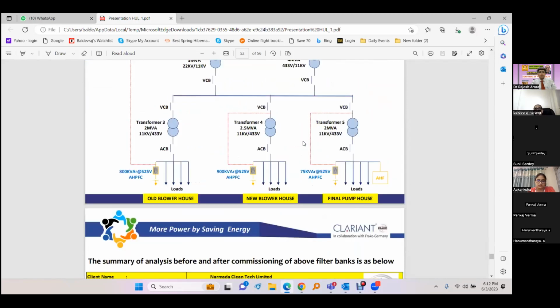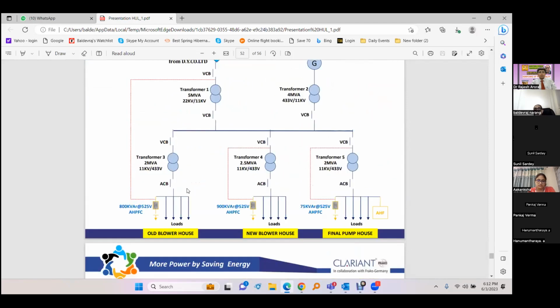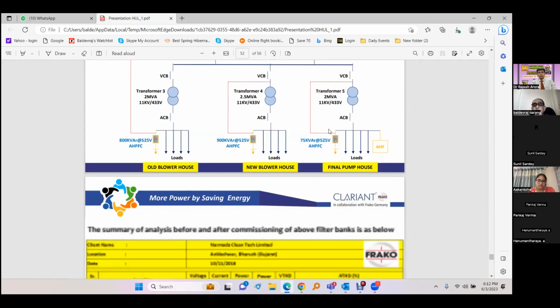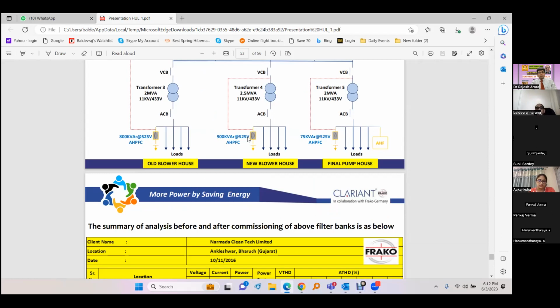Remaining, we are just giving standard solutions, meaning active and passive combined. Suppose harmonics we are not able to fully control with passive, we give some partly active filters also, and we are able to come near to the IEEE 519 norms. So this is AHF, and then we have the passive systems also. Like this is 75 kVAr passive, this is 900 kVAR passive, 800 kVAR passive is H.